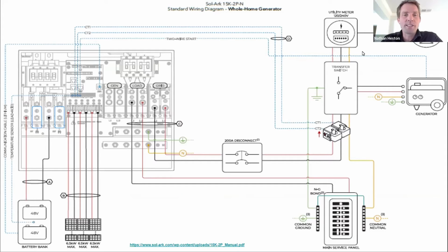I don't have quite as simple of a single line, but notice we're coming out of the grid, going in through our meter, and going through a transfer switch. We also have the 2-wire start that'll start up that generator in a grid down situation. And what our question was is, does the Sol-Ark know the difference between the generator and the grid so that settings will automatically change? How would this work? So what happens is there is a difference between a generator feed and a grid feed, and there have been a few other questions about generator frequency and following the system frequency.